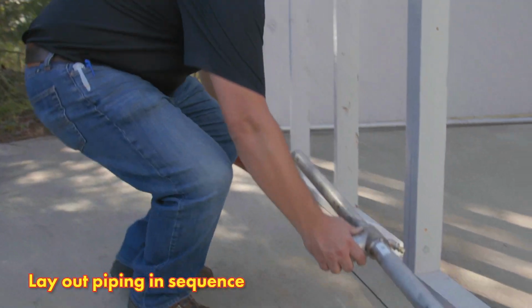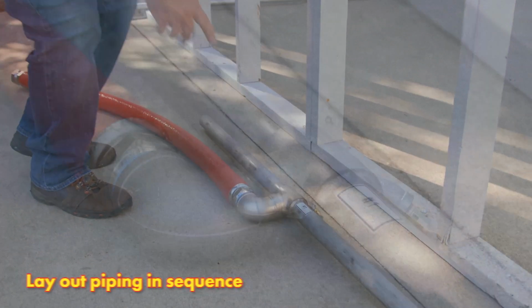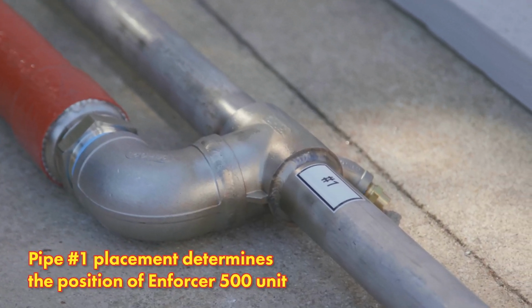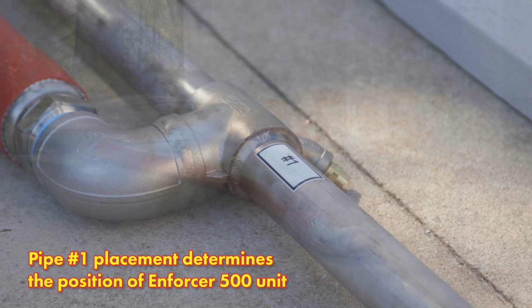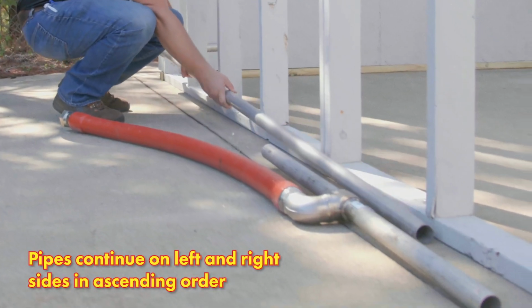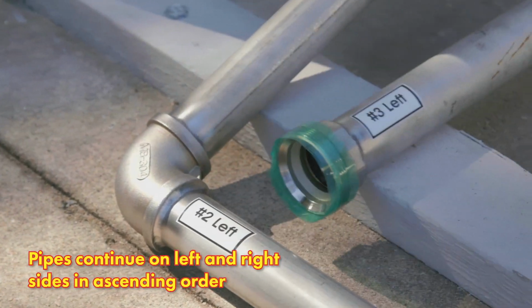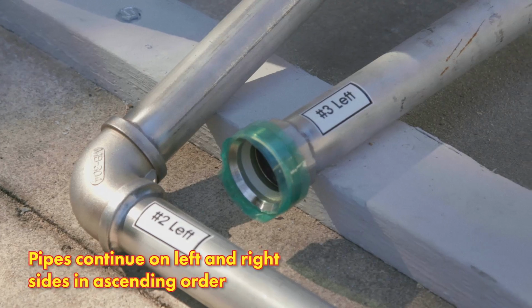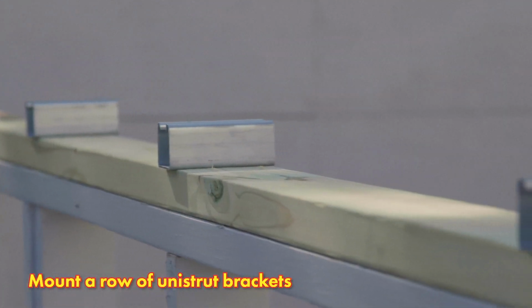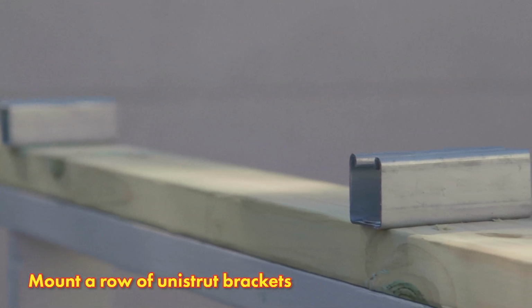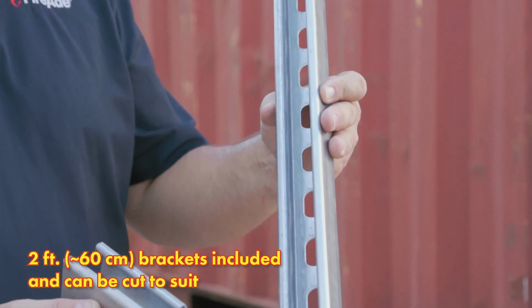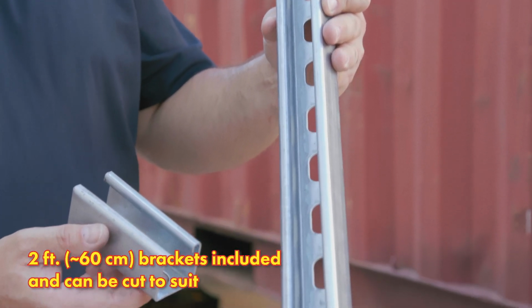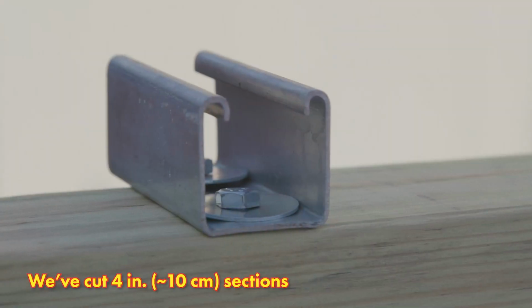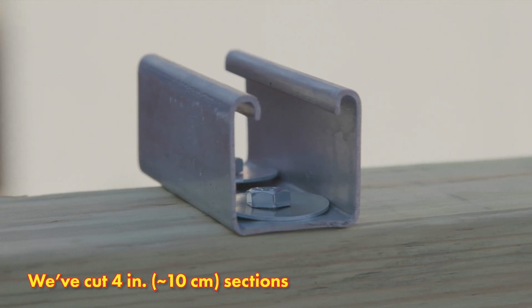To begin installation, lay out your pipe in sequence. Pipe number 1 dictates where you will position the Enforcer 500 unit. The numbers on the piping continue in sequence on both the left and right side of the number 1 pipe in ascending order. Mount a row of unistrut channel sections to install pipe number 1. 2-foot pieces of unistrut channel are included, but they can be cut to suit. In this example, we've cut 4-inch sections.